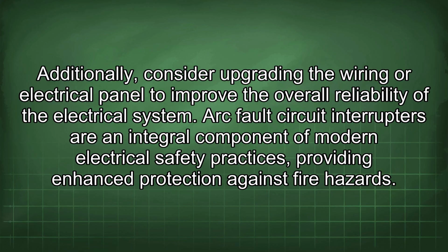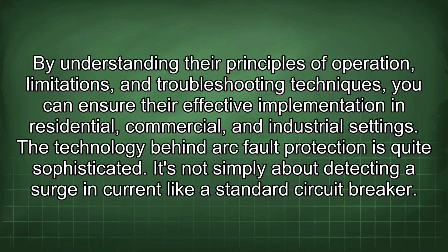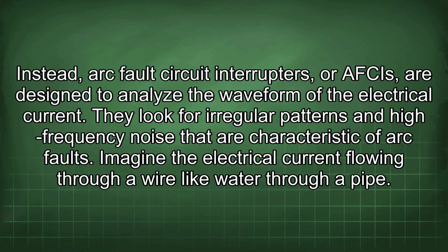Arc fault circuit interrupters are an integral component of modern electrical safety practices, providing enhanced protection against fire hazards. By understanding their principles of operation, limitations, and troubleshooting techniques, you can ensure their effective implementation in residential, commercial, and industrial settings. The technology behind arc fault protection is quite sophisticated. It's not simply about detecting a surge in current like a standard circuit breaker. Instead, arc fault circuit interrupters, or AFCIs, are designed to analyze the waveform of the electrical current. They look for irregular patterns and high-frequency noise that are characteristic of arc faults.